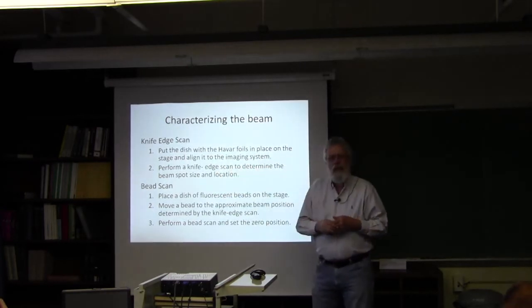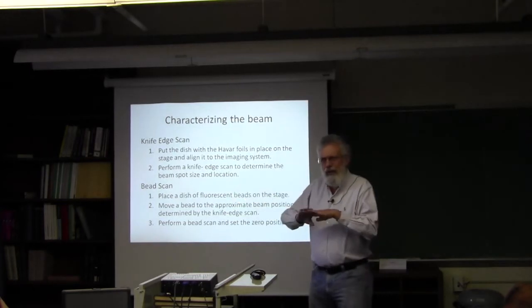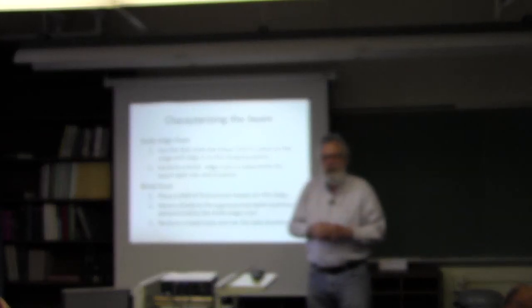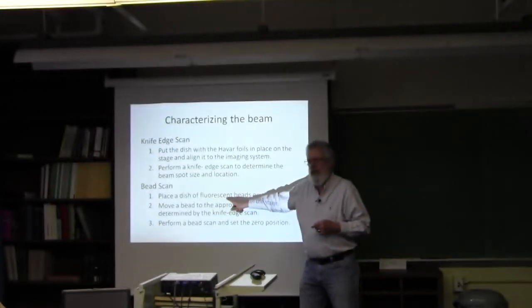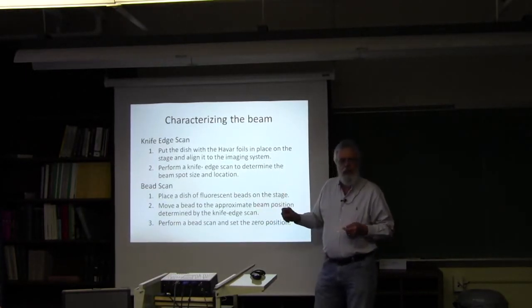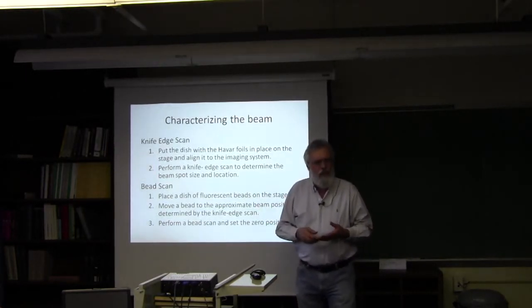You do that in each direction, and that gives you the spot size and its location. Then what you can do is look down your microscope, you put it in the location that was found here, you look down the microscope and you say that cross point is where the beam is. Then you put another dish on that has fluorescent beads in it. These are things you can see with our fluorescent microscope, but when a particle goes through, energy is lost.